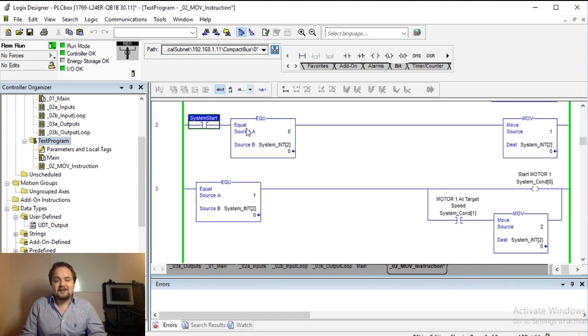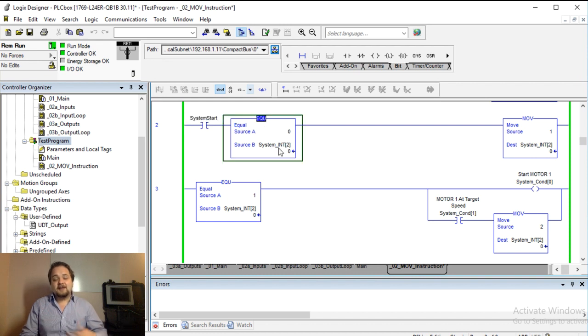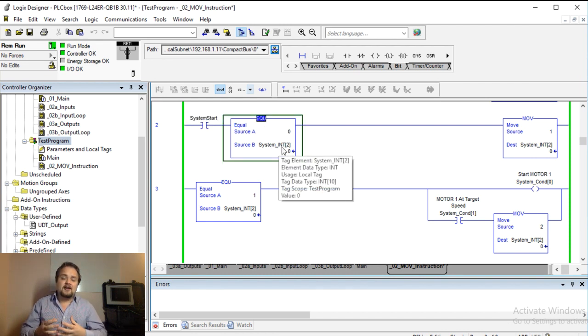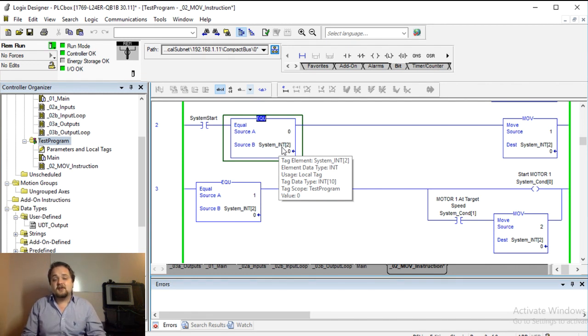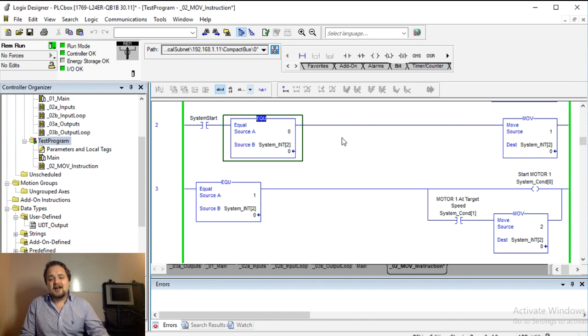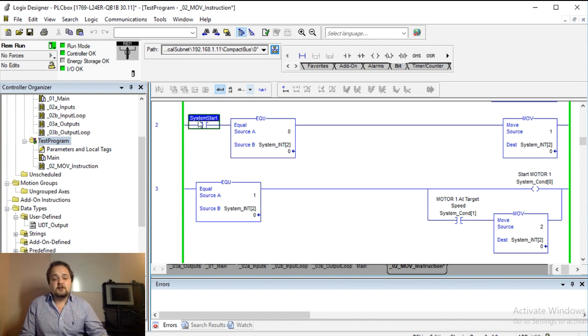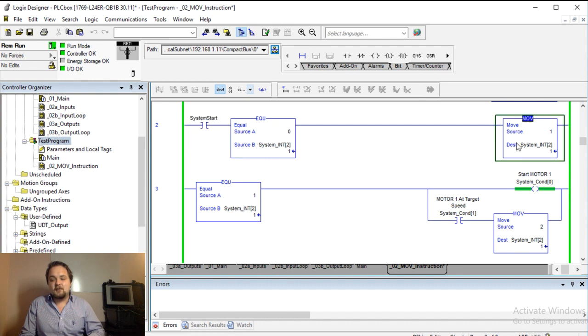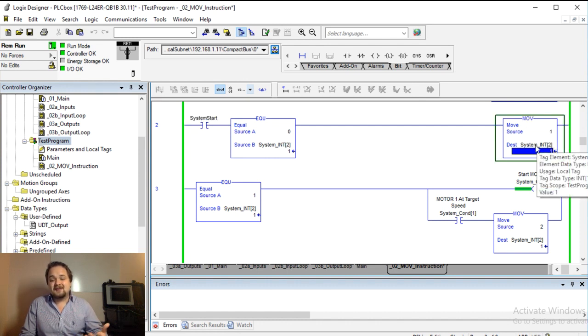In my first rung I have this system start bit, and if my system int two, which essentially think of that as my register for the status of the system, if it's equal to zero, we are going to allow the system to start. So I'm going to toggle this and as I start the system you will notice that the move instruction executed. It moved this one into this system int two.